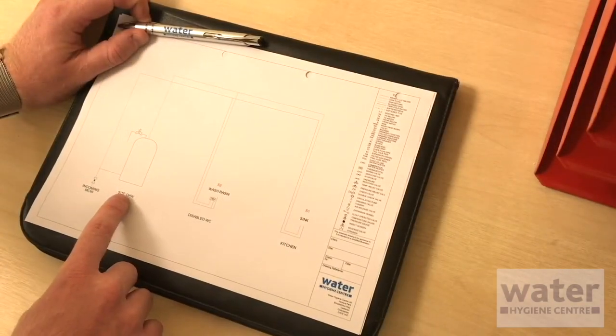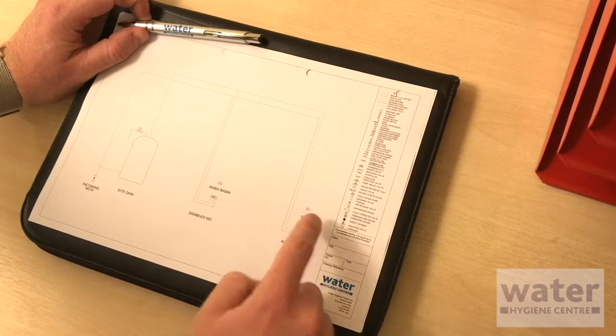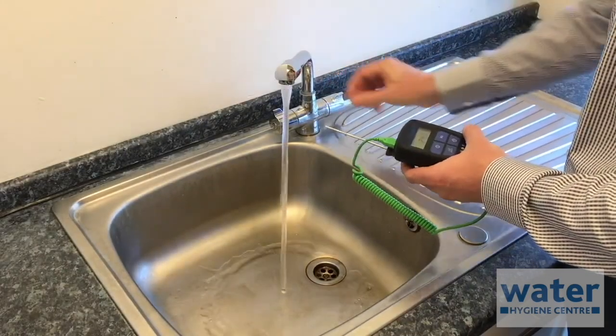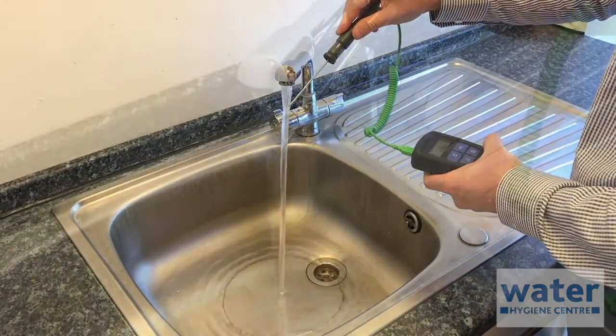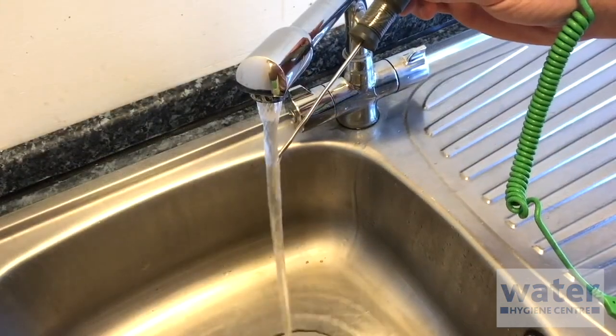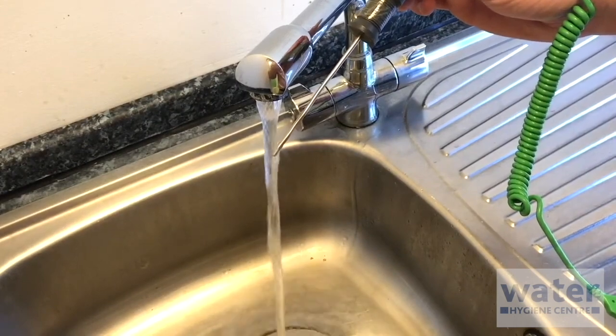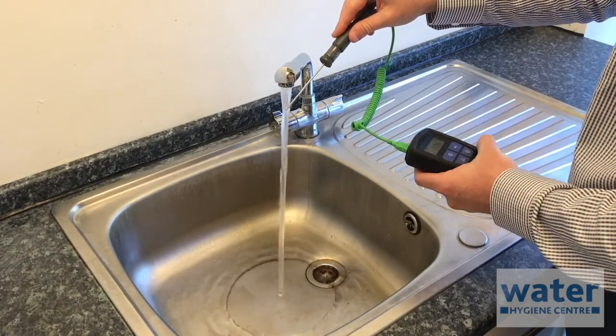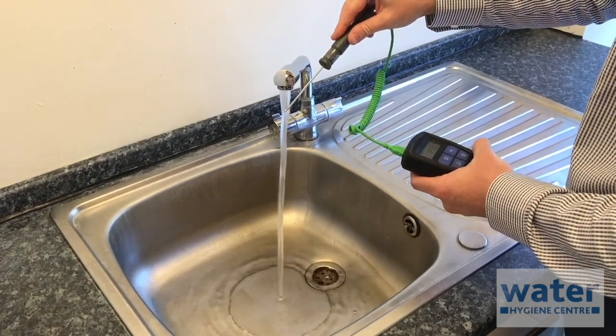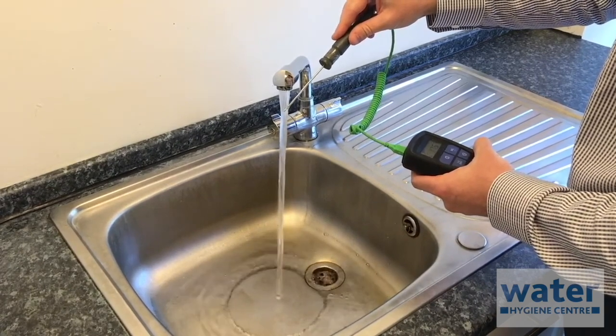To begin, use the schematic to help you identify the correct monitoring location and outlet. Ensure that the tap has a good flow and insert the immersion probe into the running water at a 45-degree angle. For cold outlets, the required temperature should be reached within 2 minutes. For hot outlets, the required temperature should be reached within 1 minute.